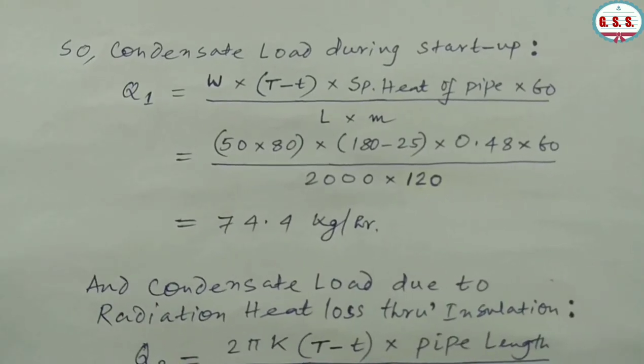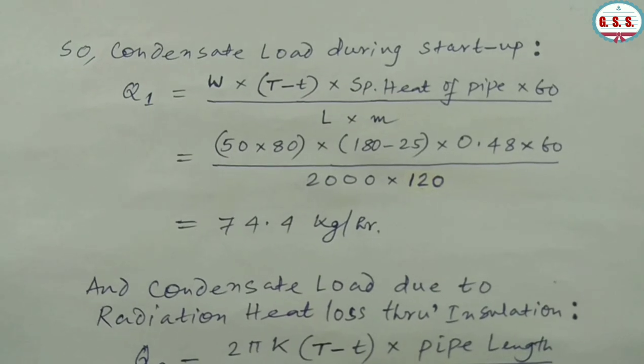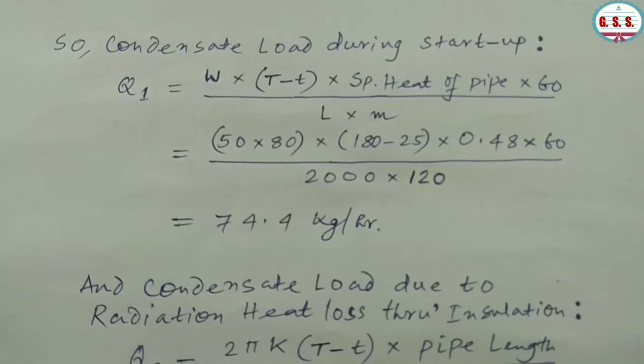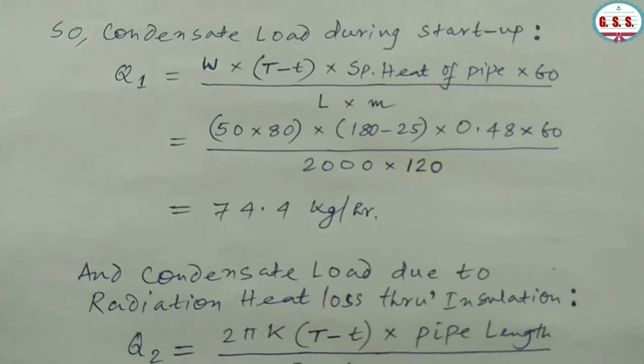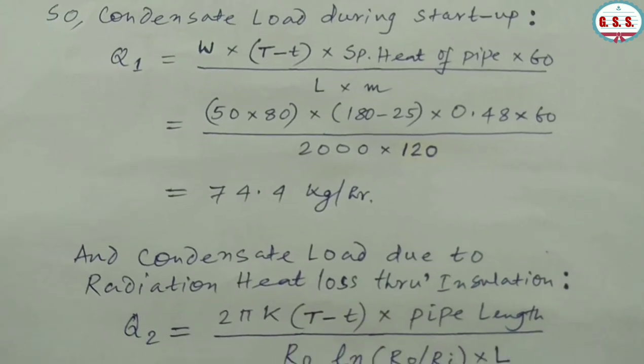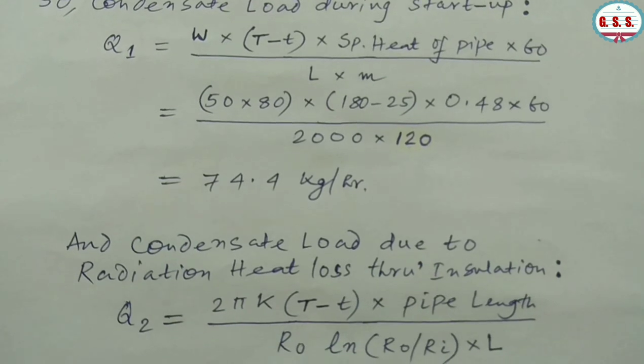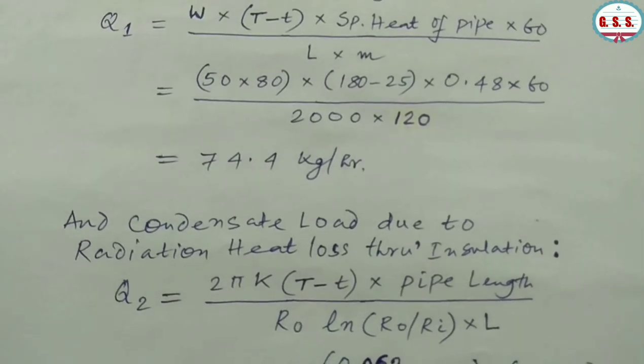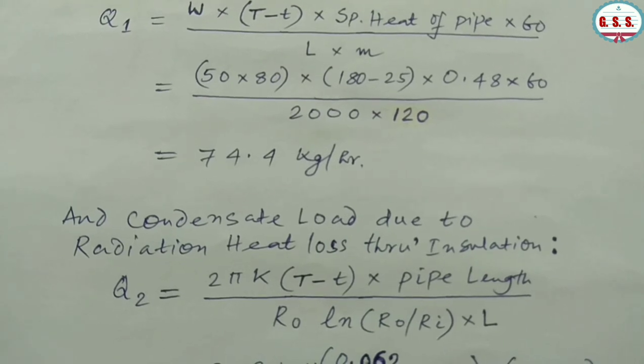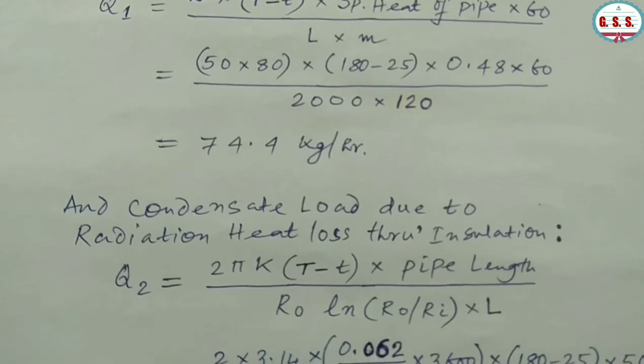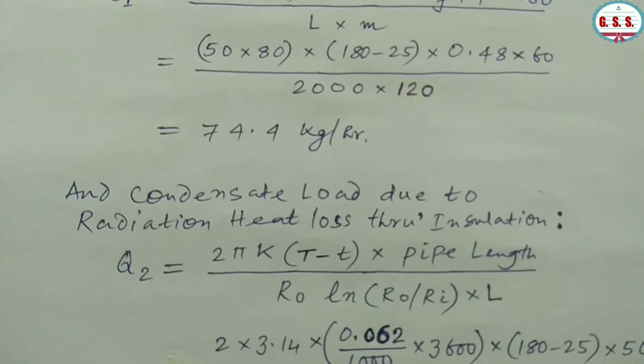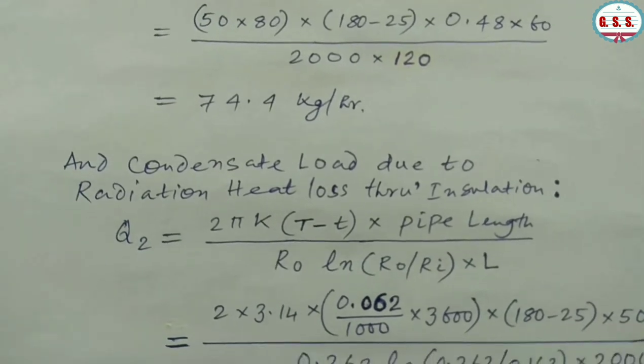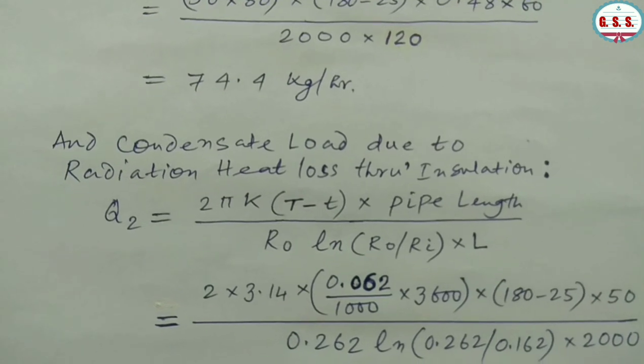Condensate load during startup: Q1 = (W × (T − t) × specific heat × 60) / (L × M) = (50 × 80 × (180 − 25) × 0.48 × 60) / (2000 × 120) = 74.4 kg/hr.